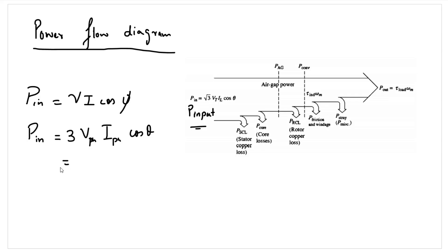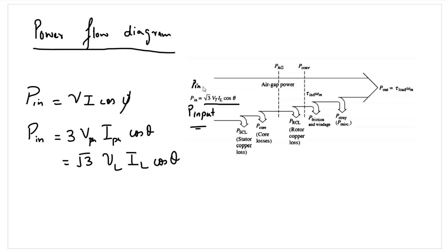Since the connections will be either in star or in delta, the phase voltage will be V_line/√3 for star, or the phase currents will be I_line/√3 for delta. Whether it's a star or delta connection, the real power equation will be √3·V_L·I_L·cosθ, where V_L and I_L represent the line voltage and line currents, and θ is the phase difference between voltage and current. For a single-phase induction motor it is simply V·I·cosθ.